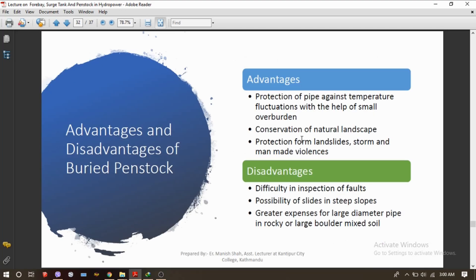Now, what are the advantages and disadvantages of buried penstock? Since it is buried, it is very well protected from temperature fluctuation. It conserves the natural landscape since it is backfilled with soil, and it has protection from landslides, storms, and man-made damage. The disadvantages are that inspection of faults is very difficult, there are high possibilities of sliding on steep slopes, and there is greater expense for large diameter pipes in rocky ground with large boulders.